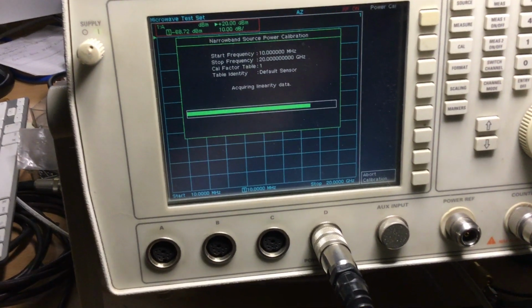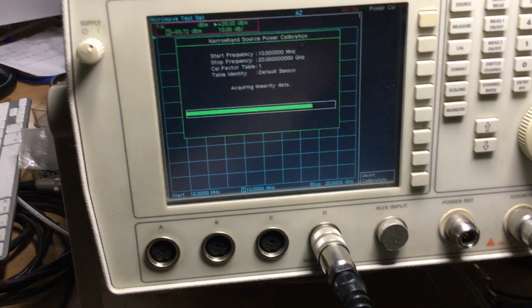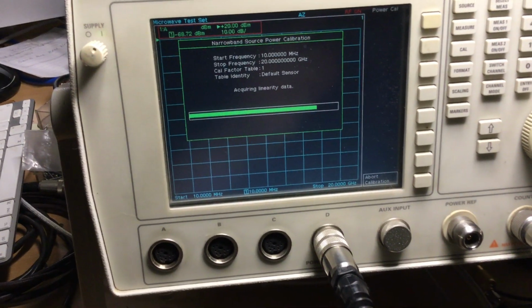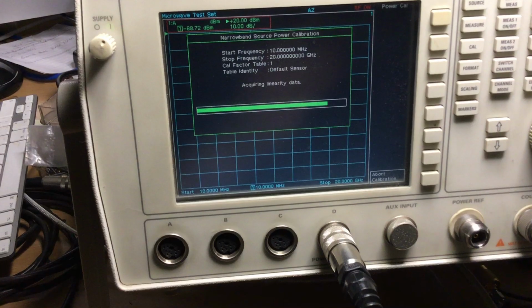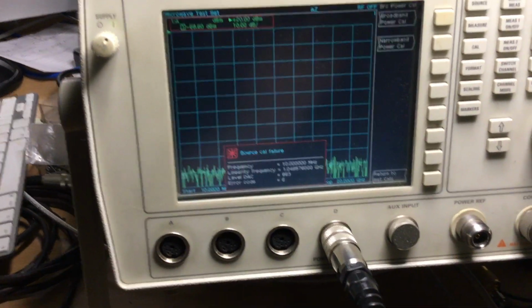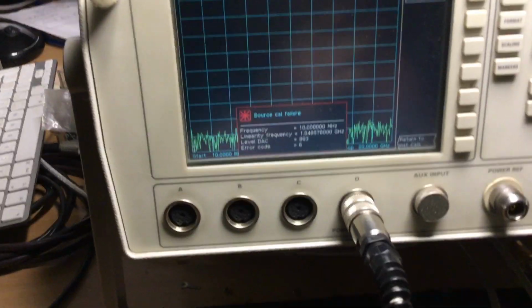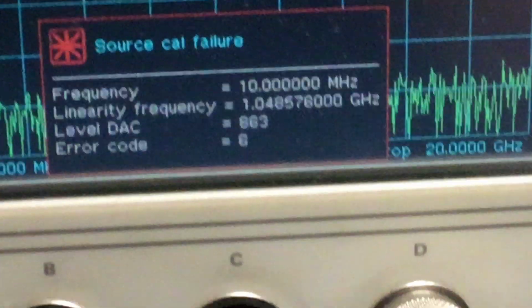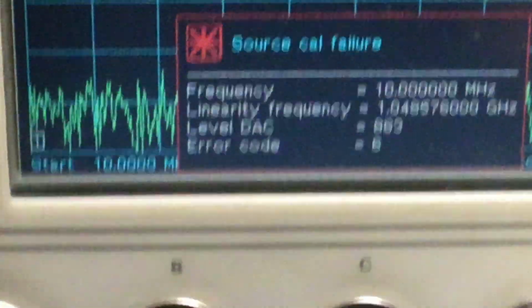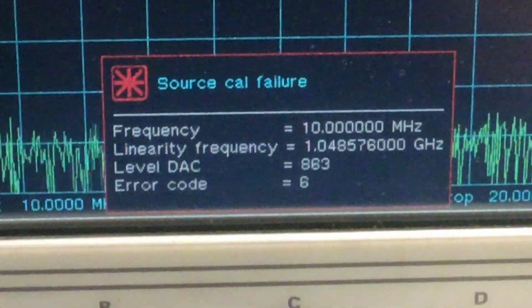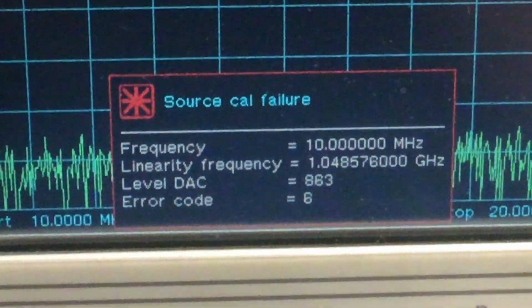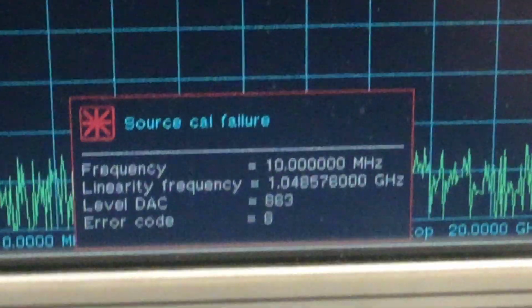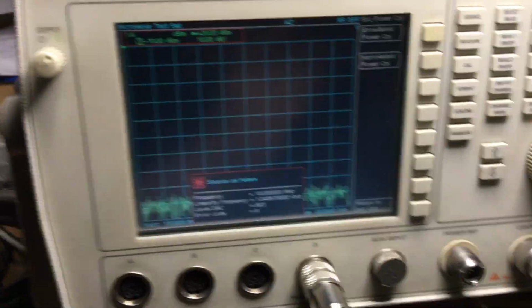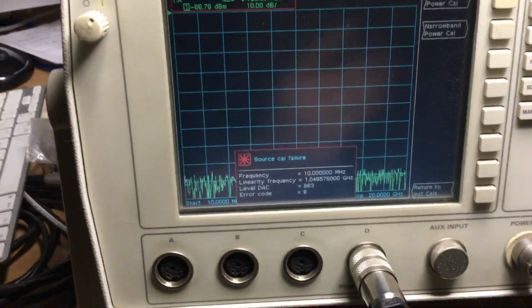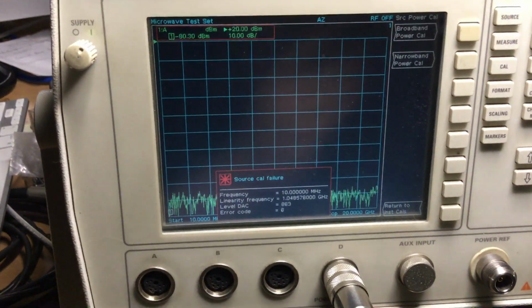As you can see, even the narrowband does take a few moments to several minutes to complete, but if you do the broadband one, which does more points across the frequency range, then it takes longer. So it's failed as we thought it would, and this is simply because, again, the DAC reading there, the level DAC is too high at that particular frequency, and that's the error code it's flagged up. So that means that diode repair that we've done isn't quite right. Although we were getting an improved control of the signal, we weren't getting a wholly controlled signal.